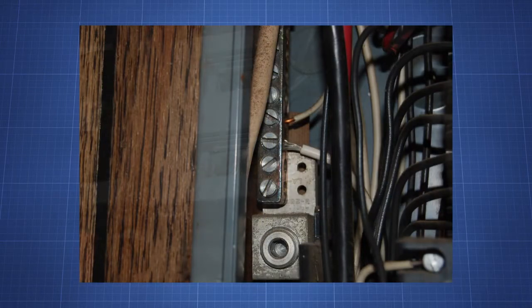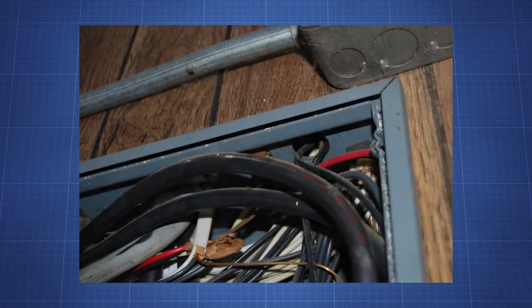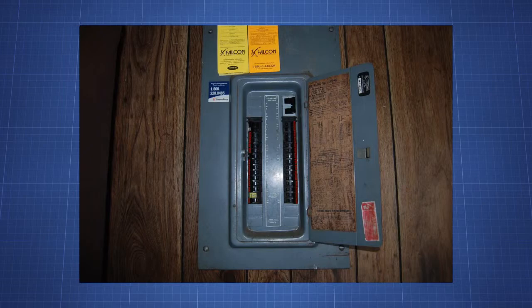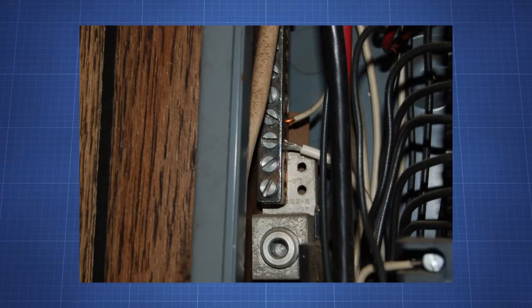They had stated in the class action lawsuit that the Federal Pacific Electric Company had violated the Consumer Fraud Act because they knowingly manufactured and distributed circuit breakers which didn't meet UL standards. What's supposed to happen with these panels is that if too much electricity goes in, the breaker trips, which stops the electric current from passing through it. Well, what happens is that some of the circuit breakers in specific Federal Pacific panels don't actually trip, so the electricity continues to move through, and there is no doubt that fires have been started as a result of these panels. So my suggestion is to have it replaced.